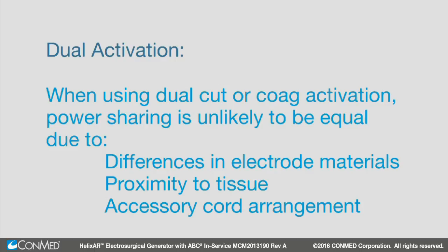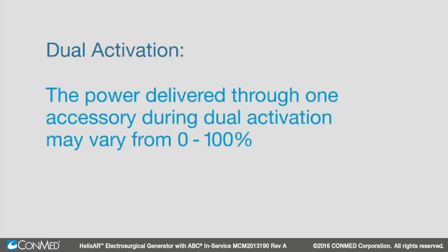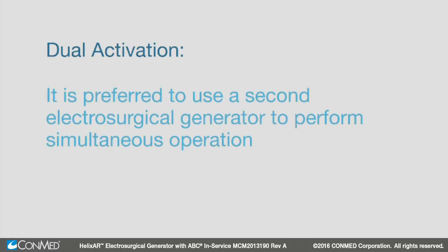Note that when using dual cut or coag activation, power sharing is unlikely to be equal due to differences in electrode materials, proximity to tissue, and accessory cord arrangement. The power delivered through one accessory during dual activation may vary from 0 to 100%. It is preferred to use a second electrosurgical generator to perform simultaneous operation.